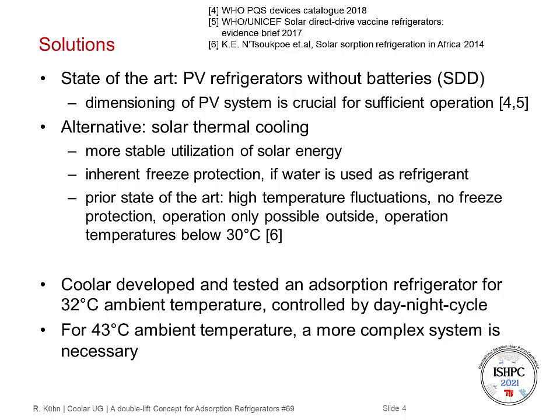In the prior state-of-the-art, there were high temperature fluctuations and no freeze protection, because methanol was used as refrigerant. Operation was only possible outside, because the adsorbent was located directly in the solar collector, and operation temperatures for sufficient cooling were below 30 degrees C ambient temperature. In the past, Coolar developed and tested an adsorption refrigerator for 32 degree ambient temperatures, controlled by the day-night cycle, where regeneration takes place during the day when the sun is shining and cold is produced during the night hours. But for 43 degree ambient temperature, a more complex system is necessary, and this is the aim of the presentation.